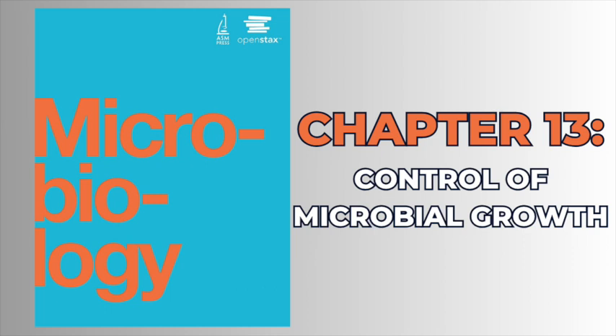Biological safety cabinets. Biological safety cabinets are a good example of the use of HEPA filters. HEPA filters in biological safety cabinets, BSCs, are used to remove particulates in the air, either entering the cabinet, air intake, leaving the cabinet, air exhaust, or treating both the intake and exhaust. Use of an air intake HEPA filter prevents environmental contaminants from entering the BSC, creating a clean area for handling biological materials. Use of an air exhaust HEPA filter prevents laboratory pathogens from contaminating the laboratory, thus maintaining a safe work area for laboratory personnel.